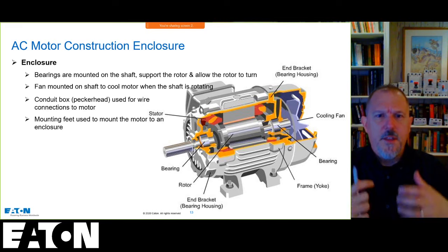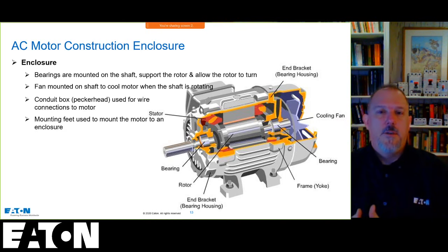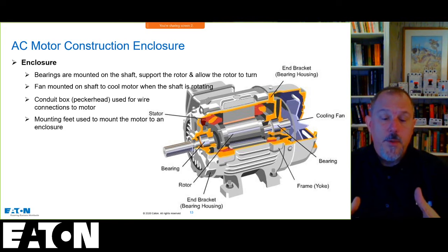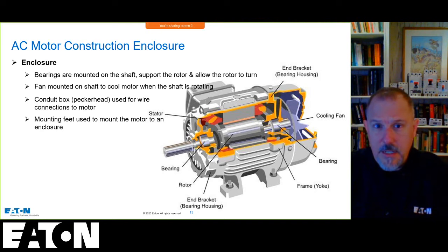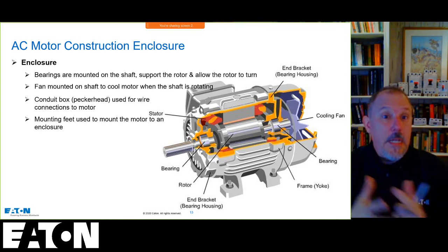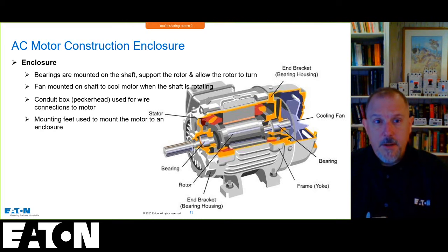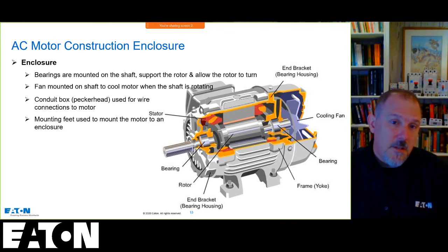As you look at the construction of a motor, you have to think about the failure parts and pieces and what would cause certain things to fail. What would cause a bearing housing to fail, or the bearings to fail, or that shaft to fail, the stator and the stator windings? You're connecting the stator directly to a power source, so transient voltages could cause those stator windings to fail. Heat could cause the insulation to break down and eventually fail as the windings come in contact with each other, causing internal short circuits. With bearings, heat and misalignment of that shaft, putting torque on it in a way it's not meant to be, could hurt your bearings and cause heat in the bearings, and the bearings could fail, which could cause other catastrophic failures inside that piece of equipment. So it's important to understand the construction of these devices because it helps us understand our protection.